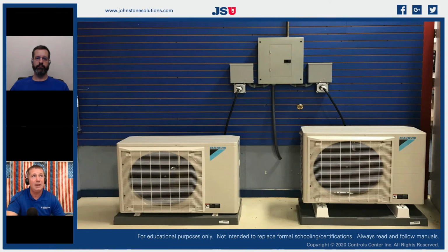I was also at one installation way out in the country in southern Indiana, and it was at the very end of a power grid, and they were running like 186 volts on the system. And so the inverter was regularly shutting itself down on an internal protection. So after using a power conditioning device on it, never heard from them again. So it was interesting that even at that low of voltage, the capacitors had the ability to store enough and to help bring those peaks and valleys.